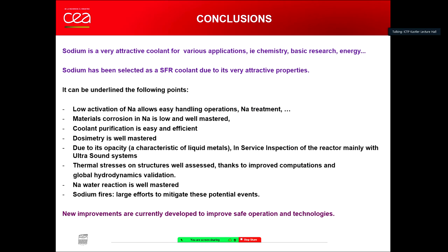And so we have a low activation of sodium. This is important point. Okay. Material corrosion is very low. We have some discussion this afternoon. Dosimetry is well mastered, generally, in our systems. Opacity, due to opacity, but it's not specific of sodium. It's always true for all liquid metals. We need to develop technologies based often on the ultrasonic technologies. Thermal stress, some structure are well assessed, but effectively, liquid metal in a metallic structure, you have some impact. You need to address this environmental effect on the structures.